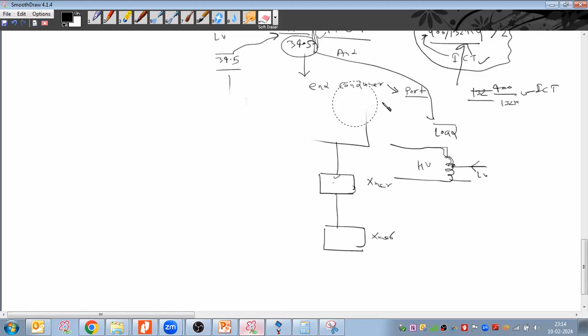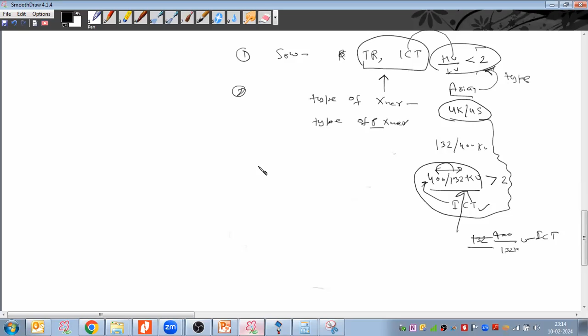Also, one thing: actually, if there is a transformer in the downstream for the station load, the auto transformer is okay. For example, for this 34.5 kV station load, we will take a 2-winding transformer, we will not take this. That transformer should be connected to this 34.5 kV; the primary of the station transformer will be connected to the 34.5 kV, as you mentioned. Yes, so that is also going to feed load only, correct.